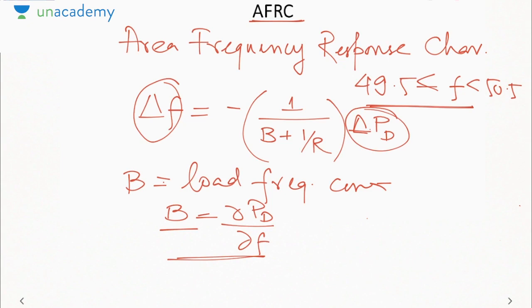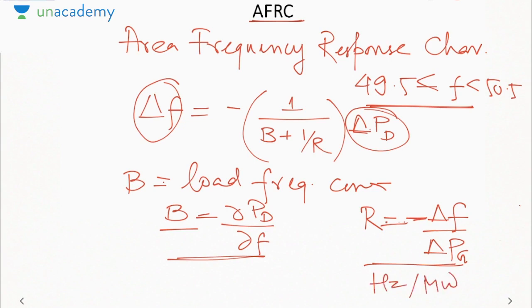Similarly, R indicates how much the generation is sensitive with the change in frequency. So R is actually minus delta F by delta Pg. Okay, because we know with increase in the power output of a machine, frequency goes down. That is why we are using a negative sign. So what will be the unit of R? It will be hertz per megawatt. What will be the unit of B? Megawatt per hertz. Okay, so these two parameters combined will give me AFRC, area frequency response characteristics.